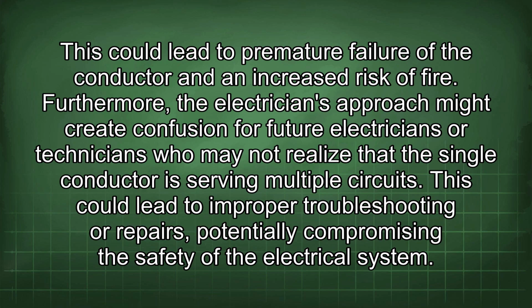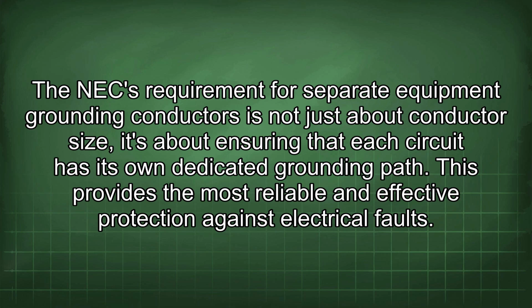Furthermore, the electrician's approach might create confusion for future electricians or technicians who may not realize that the single conductor is serving multiple circuits. This could lead to improper troubleshooting or repairs, potentially compromising the safety of the electrical system. The NEC requirement for separate equipment grounding conductors is not just about conductor size, it's about ensuring that each circuit has its own dedicated grounding path. This provides the most reliable and effective protection against electrical faults.